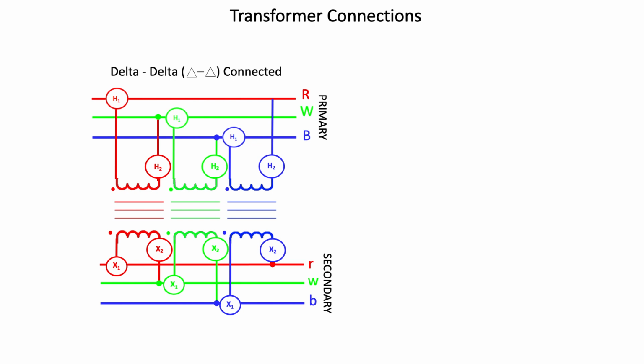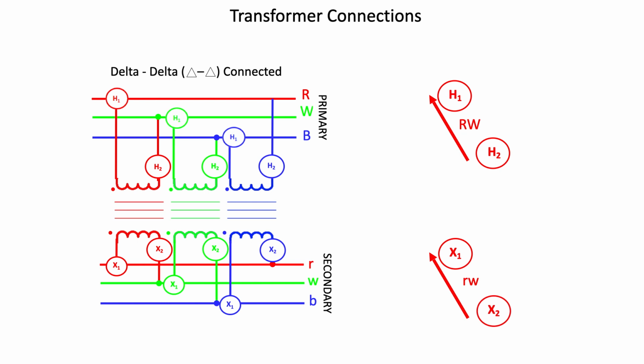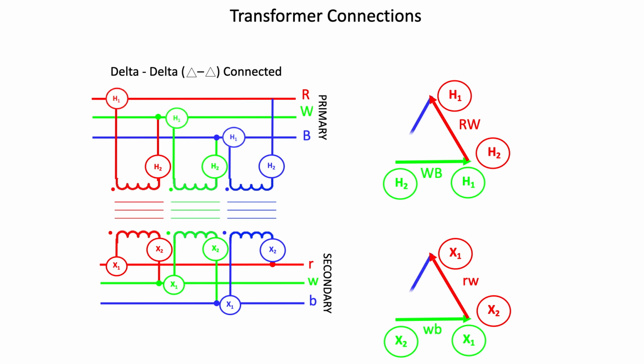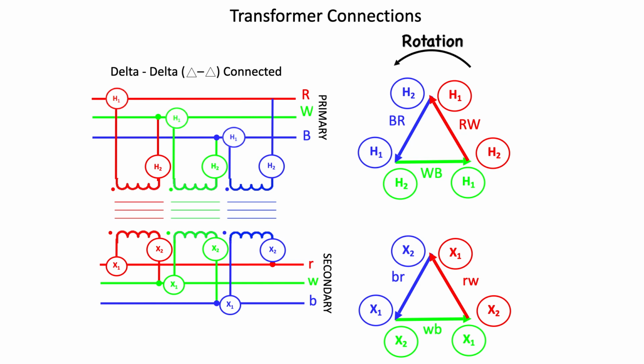The vectors or phasors look like this, both primary and secondary. We'll put them both up at the same time because they're connected the same way or similar way. The red to white phasors, phase to phase, are shown here. The white to blue phasor is shown like this, and the blue to red phasor, both the primary and secondary, are shown like this. All of these phasors, of course, are rotating counterclockwise. You'll notice that there is no neutral connection in a delta-delta connection.